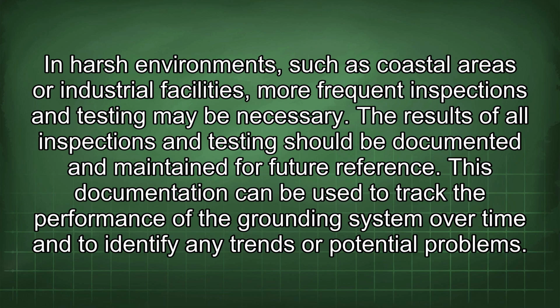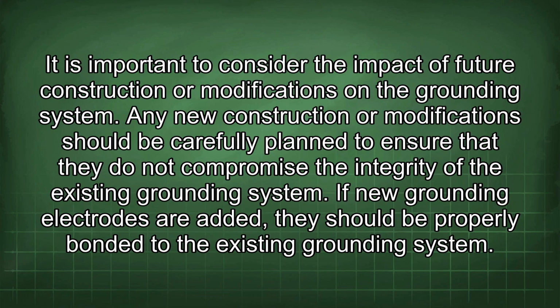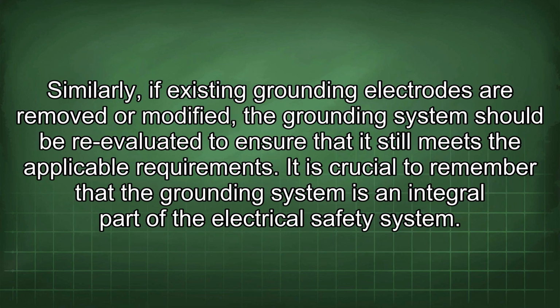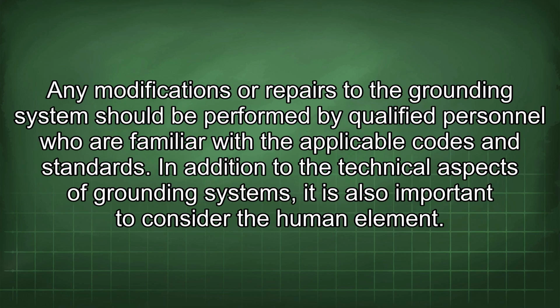It is important to consider the impact of future construction or modifications on the grounding system. Any new construction or modifications should be carefully planned to ensure that they do not compromise the integrity of the existing grounding system. If new grounding electrodes are added, they should be properly bonded to the existing grounding system. Similarly, if existing grounding electrodes are removed or modified, the grounding system should be re-evaluated to ensure that it still meets the applicable requirements. It is crucial to remember that the grounding system is an integral part of the electrical safety system. Any modifications or repairs to the grounding system should be performed by qualified personnel who are familiar with the applicable codes and standards.